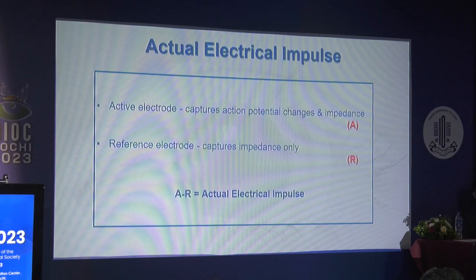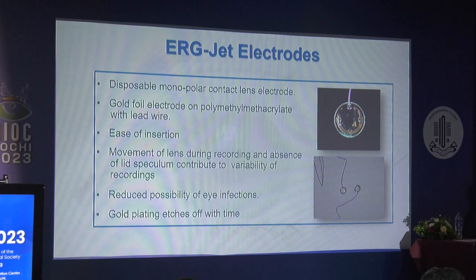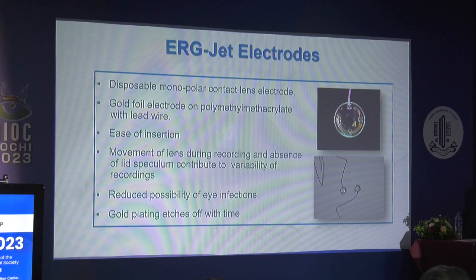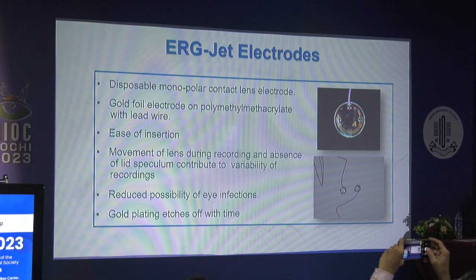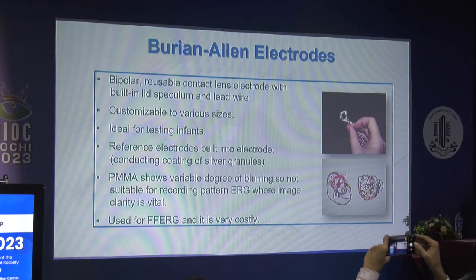Recording by active electrodes can be done by conductive fibers, foils, conjunctival loop electrodes, or contact lens electrodes — which are centrally transparent with an optical opening, giving the best and most stable recording with highest amplitude. Different types of active electrodes include skin electrodes (mainly used in children), corneal ERG electrodes (monopolar like jet contact electrodes, or bipolar like Burian-Allen electrodes), DTL electrodes (most commonly used), and gold foil electrodes. The reference electrodes are incorporated into the contact lens speculum assembly in bipolar electrodes for stable electrical configuration. Reference and ground electrodes can be placed near the orbital rim, ear, or forehead.